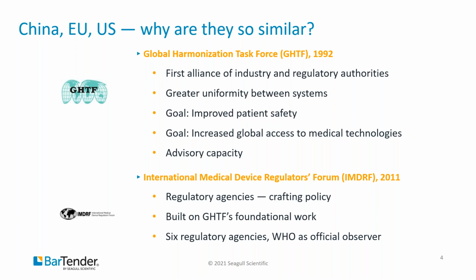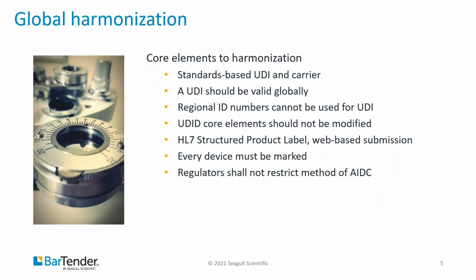So what do the core elements defined by IMDRF look like? Remember, their goal was to create a harmonized system. So the elements include the UDI and UDI carrier. The data carrier is a 1 or 2D barcode, RFID tag, NFC, any auto ID data carrier. They're based on standards. A UDI applied to a medical device anywhere in the world should be able to be used globally and to meet the UDI requirements of its regulatory authority.